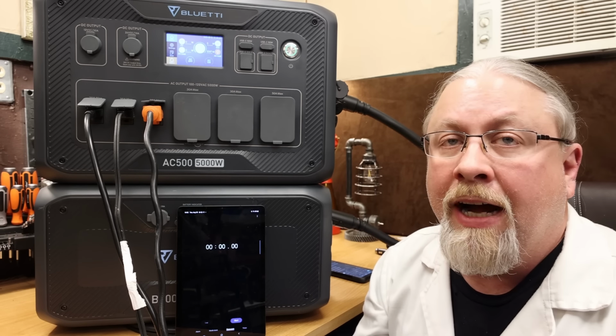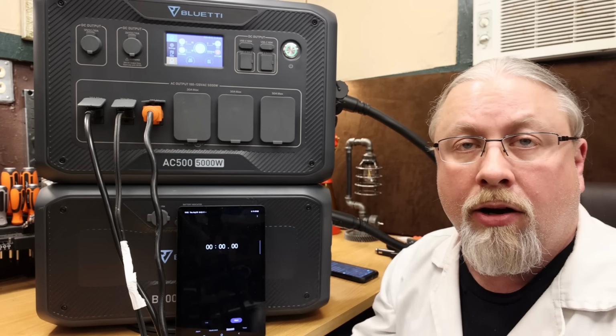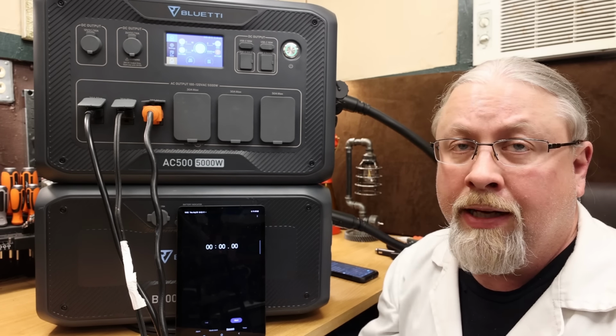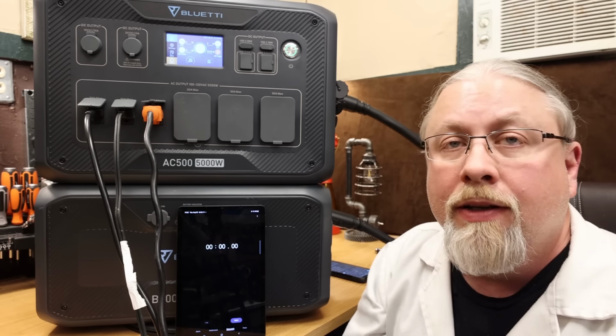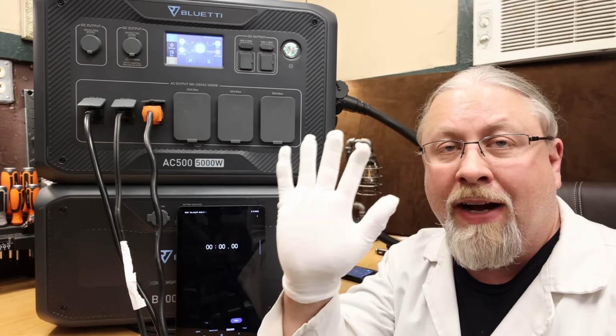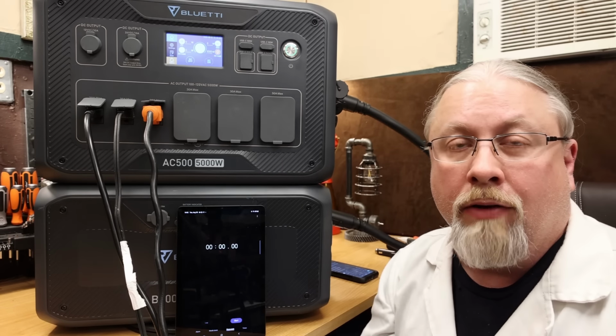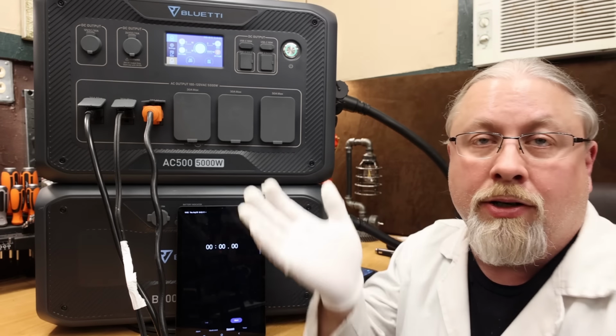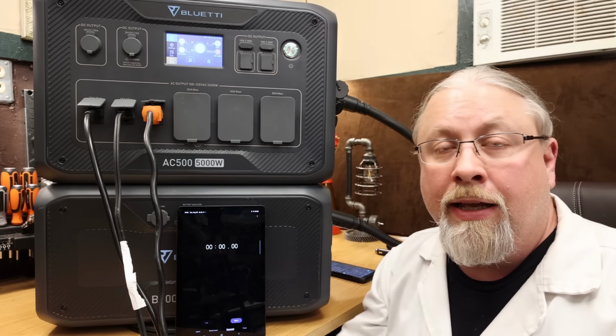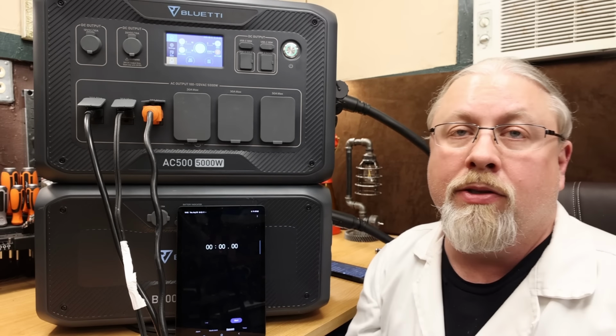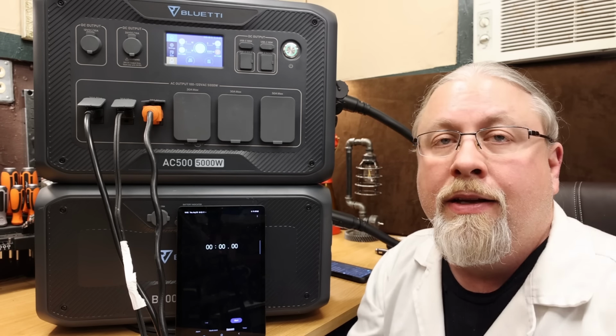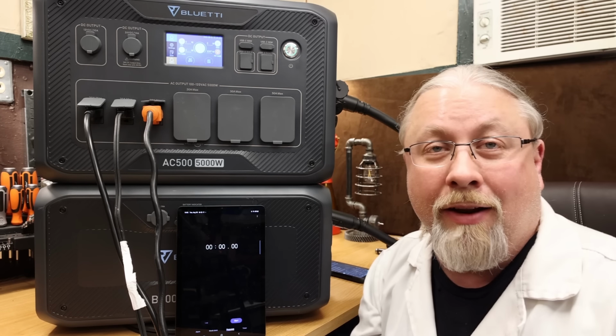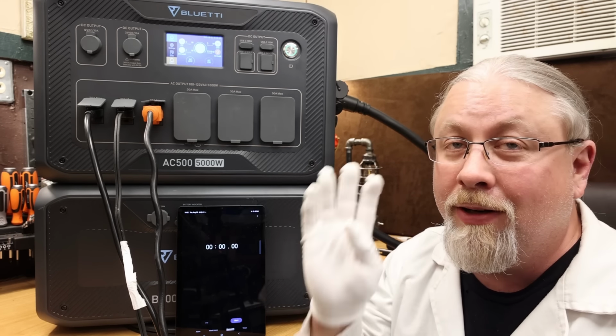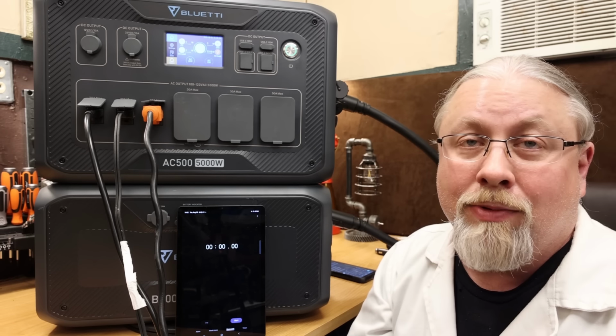Next test is the 5-minute sustained cooling, or what I call the heat soak test. This is where we run the inverter at or above its rated capacity for at least 5 minutes to see if it overheats, starts smoking, does anything out of the ordinary, makes weird noises, or starts smelling funny. I currently have this running at 5,400 watts, which is 400 watts above its rated capacity.